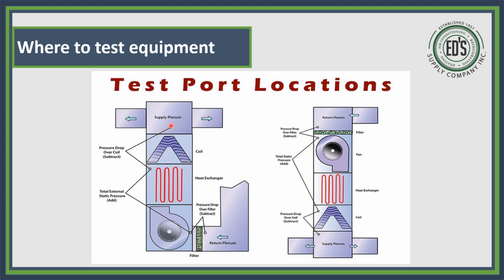And then you also want to come up here. So technically, when I'm doing it and there's no space right here, I don't want to risk drilling a hole in my furnace or damaging my heat exchanger, because this reading here would definitely be different if that's a wet coil. Dry coil, it's going to be kind of close. But I want to see what my unit and my coil are doing as one, because if you have an air handler, the coil's already in the air handler.